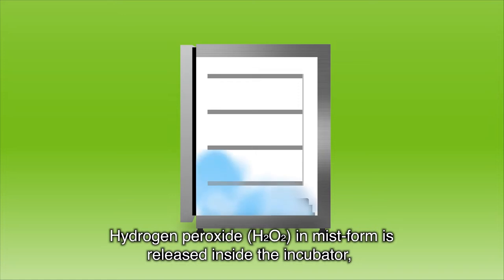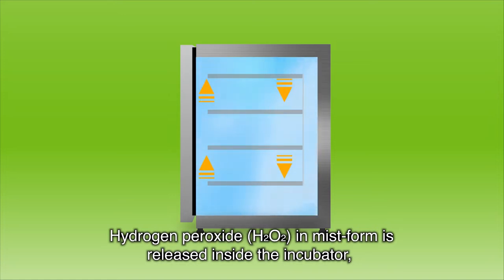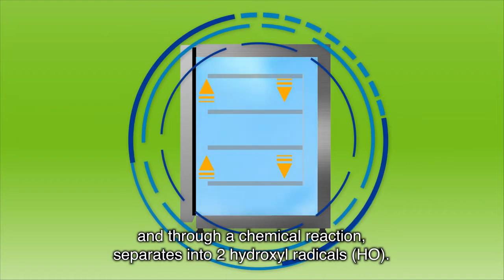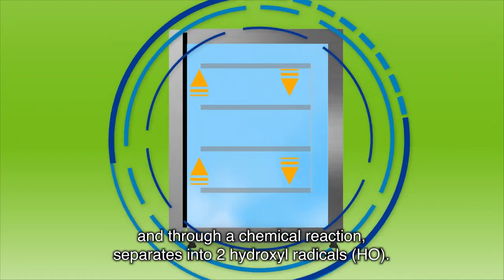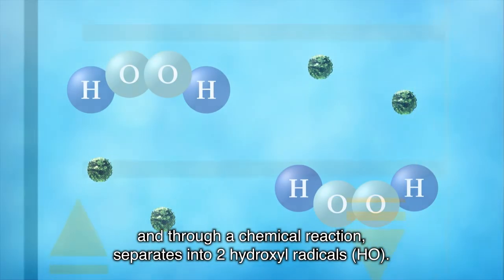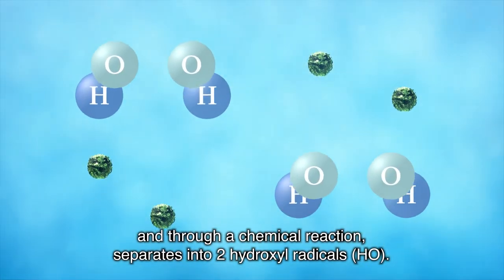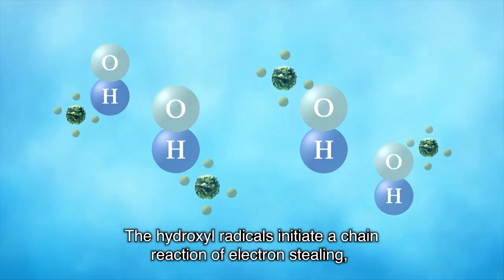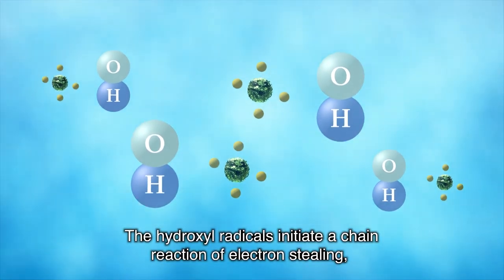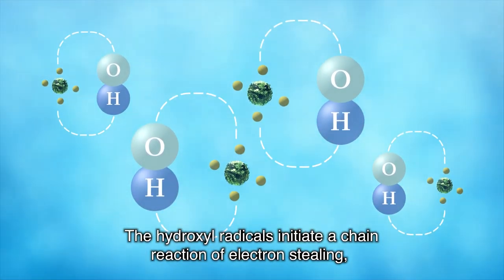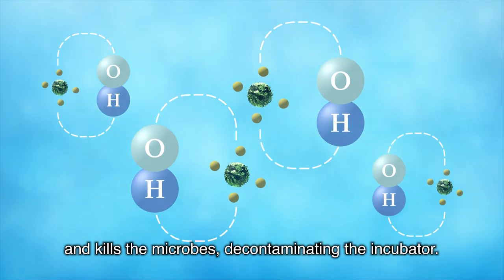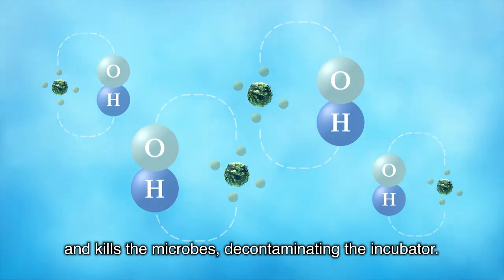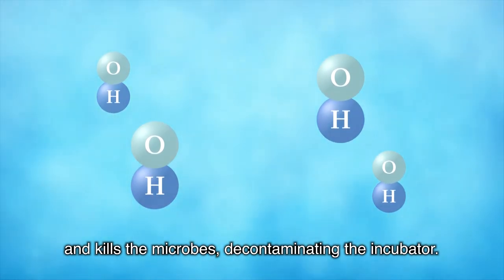Hydrogen peroxide H2O2 in mist form is released inside the incubator and through a chemical reaction separates into two hydroxyl radicals, HO. The hydroxyl radicals initiate a chain reaction of electron stealing and kills the microbes, decontaminating the incubator.